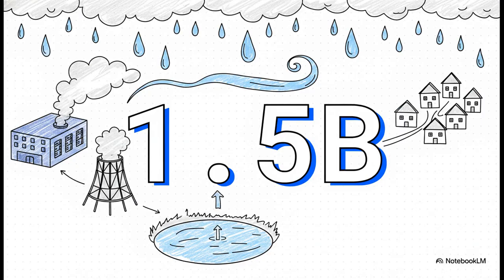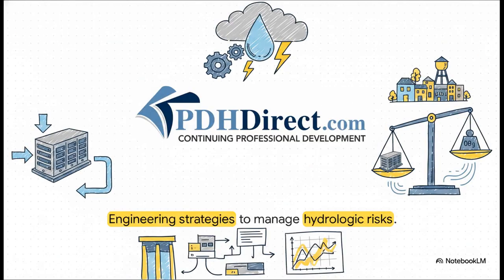To put the scale of this problem into perspective, a standard 100 megawatt data center using traditional evaporative cooling can evaporate anywhere from 500 million to 1.5 billion gallons of water every single year. That's a staggering amount. We're talking about the annual water usage of thousands of local households, just vanishing into thin air year after year. But listen, it absolutely does not have to be this way.